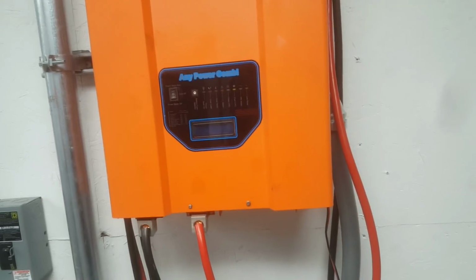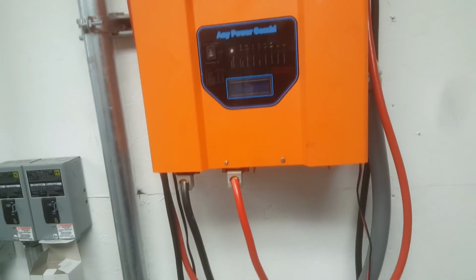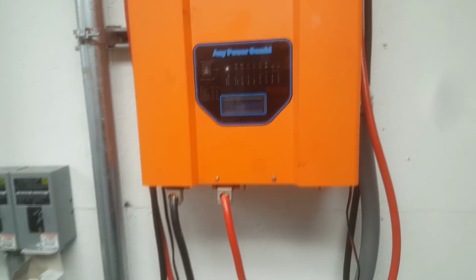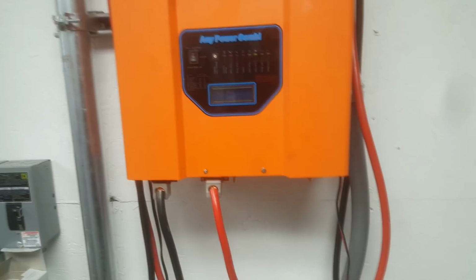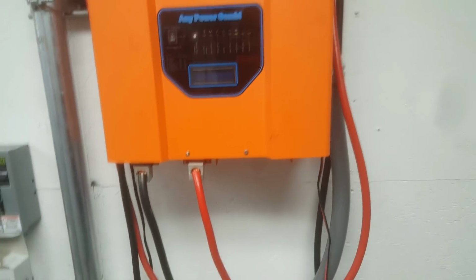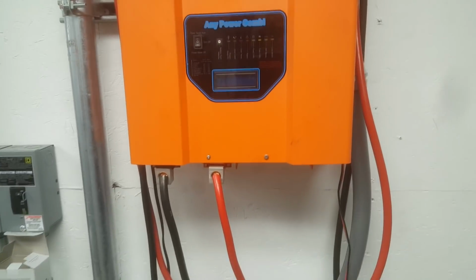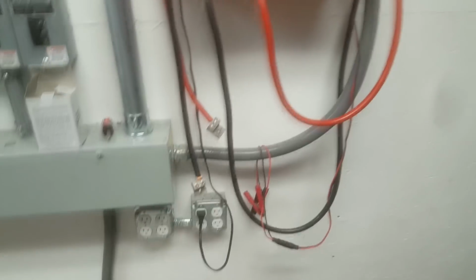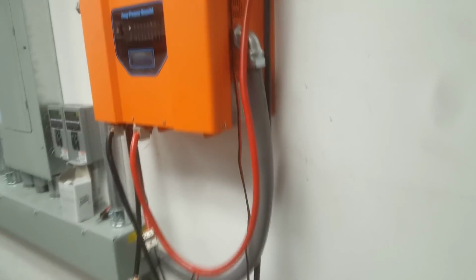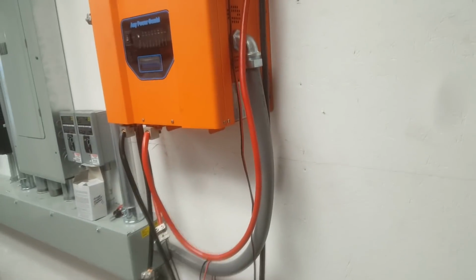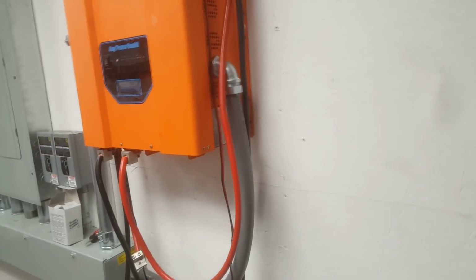Here I have a 3000 watt inverter that is also a 120 amp 12 volt battery charger, and I use this if I need to pull batteries out of the rack to better balance them out and equalize them. Say one battery is reading a low voltage, I can yank it out of the rack, put it on this charger, give it a nice full charge. And I also have an outlet down here that is off of this inverter that can be used to discharge a battery if I have a circumstance where I need to do so.